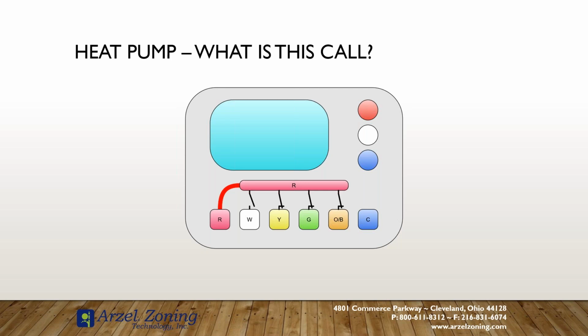All right, so something to keep in mind with the RSL panel, from the thermostat, doesn't matter what RSL panel you are using, your reversing valve is always energized on a call for cooling from the thermostat itself. So when I have a thermostat, I have a heat pump system. If my O terminal from the thermostat is energized, that has to be a cooling call. Now, even if you have a piece of equipment where the reversing valve is energized in heating, you got Rheem Ruud or something like that, even though that specific piece of equipment requires a reversing valve energized in heating, from the thermostat, the RSL panel always has the reversing valve energized on a call for cooling. And then through the panel itself, we control your reversing valve function to your equipment.